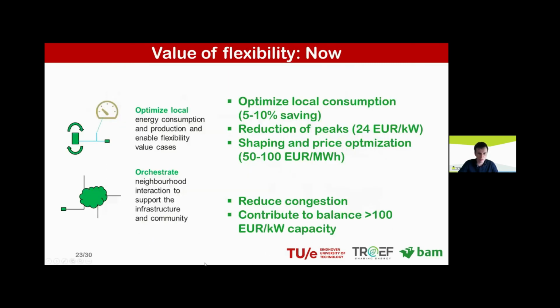Let's get to the next sheet, because Shalika told us that obtaining data is not for free. You need to think of your sensors, and I also touched upon this at the beginning. So let's take a look at the value: what can we actually get from using this flexibility? I already mentioned 5 to 10% energy savings, and this depends a lot on how much flexibility you can obtain, which depends on the buffers and subsystems Shalika introduced. To give you an impression, if you have a heating storage vessel in a regular house, you can expect about 1 to 1.5 kilowatts, and 1.5 kilowatt hours of buffering capacity.